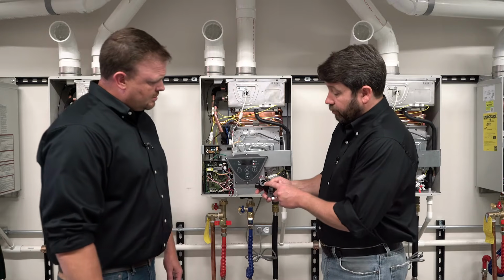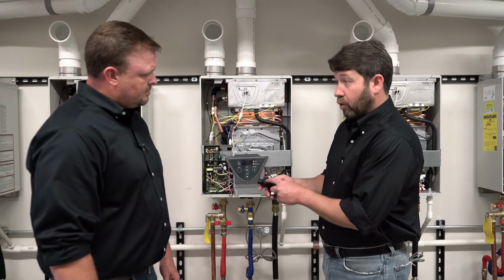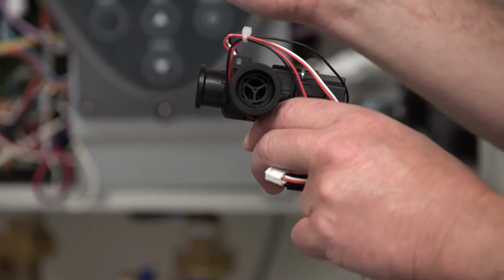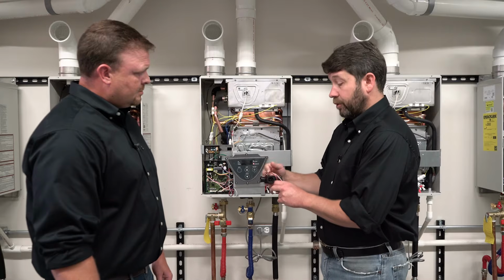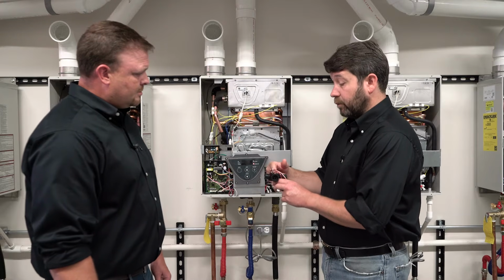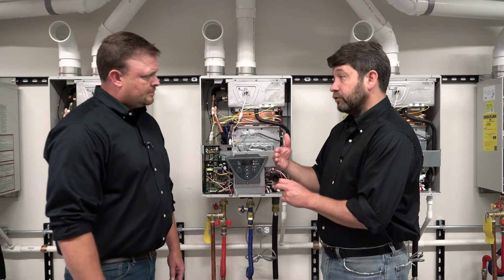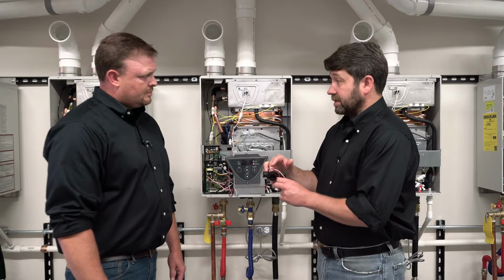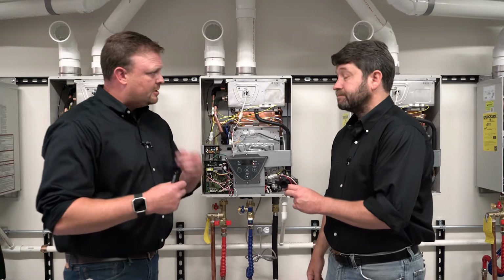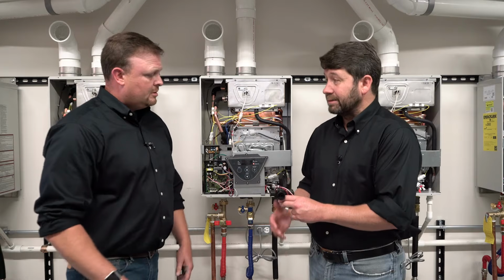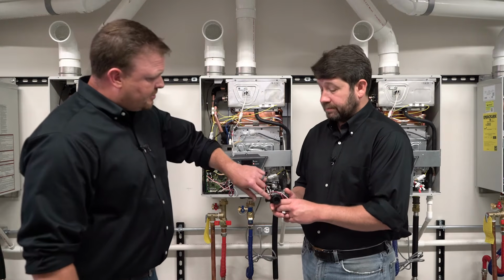And coming in, we've got a little holder here that's holding the impeller in place. And those have a little bit of a slant to them, and they put a spin on the water as it comes through here, and that's what actually turns the wheel. Okay. And coming back the other way, there's no spin on the brackets that hold it on the backside, so it wouldn't spin the impeller. You would never see flow. Correct. Okay. So that's one of the things that can happen.